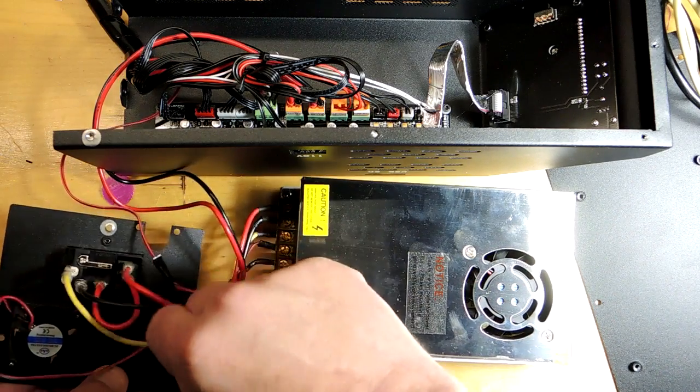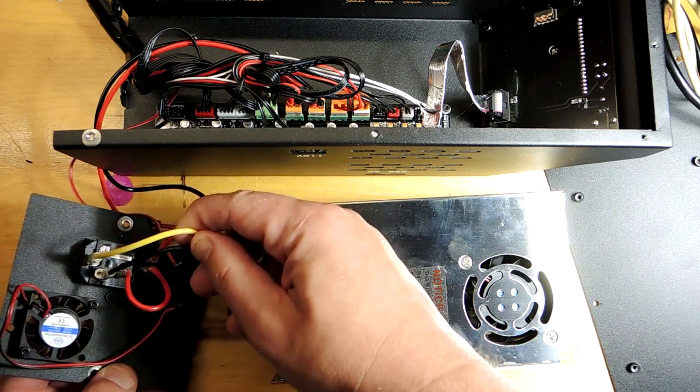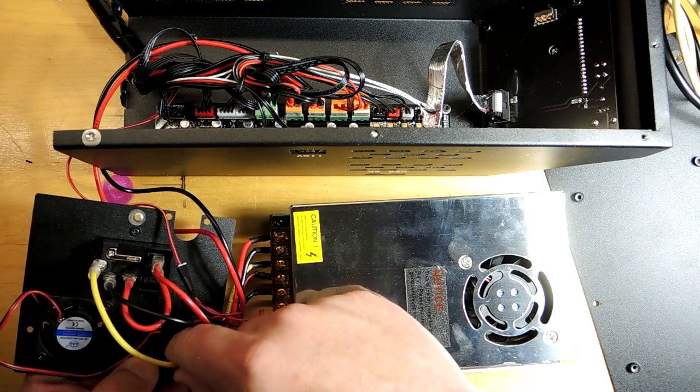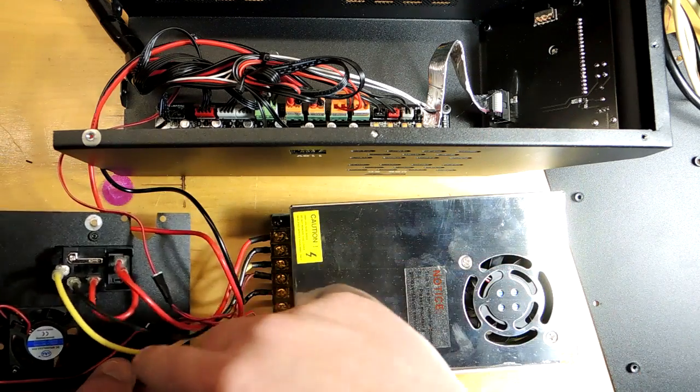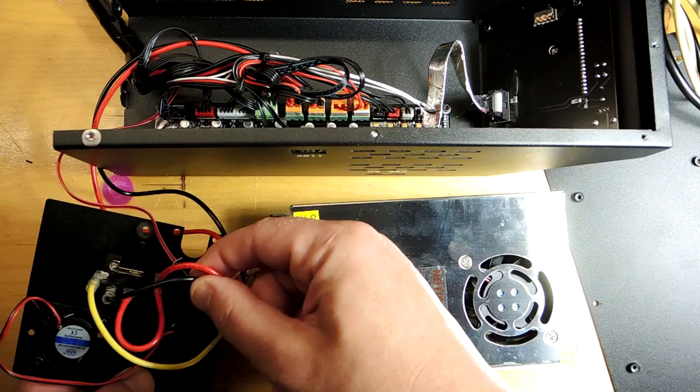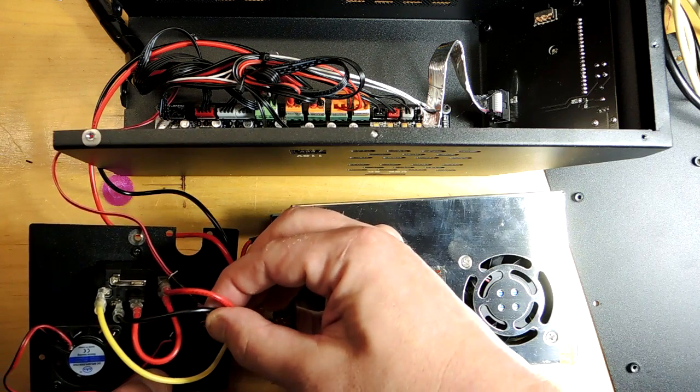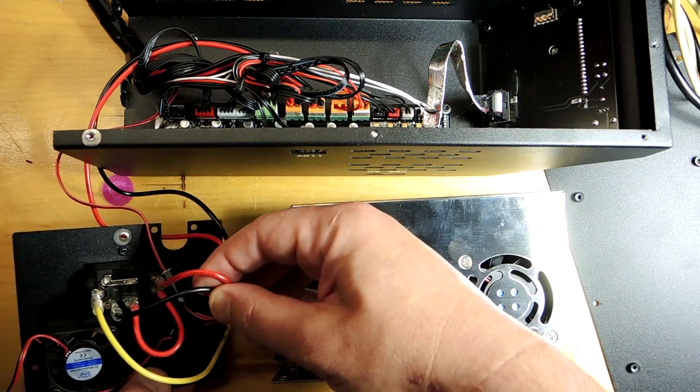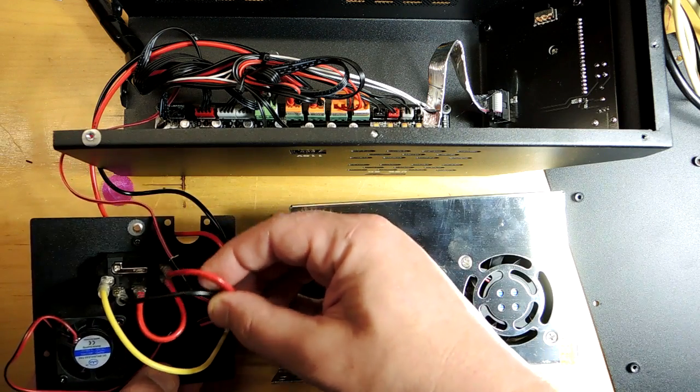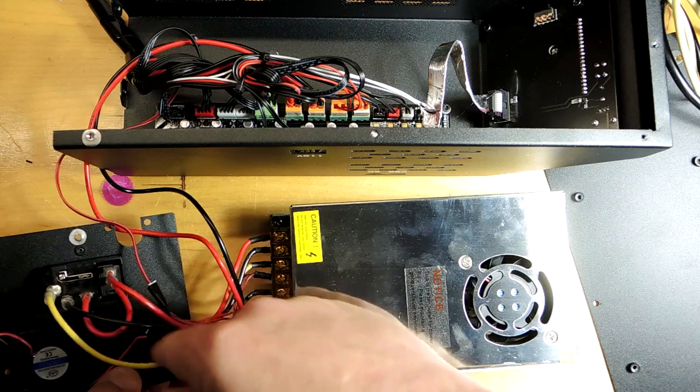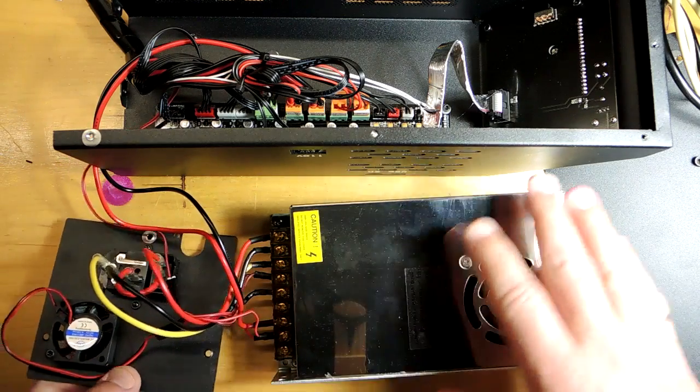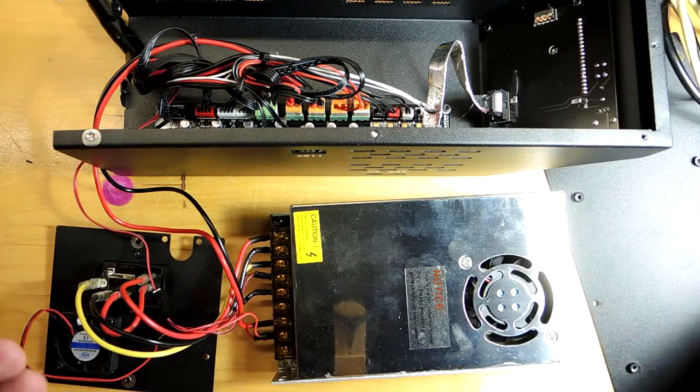The AC entry is here. The wire here is yellow. If it was European standard, it should be green with a yellow stripe. If it's North America, it should be green. So it's the wrong color, but so what? The same thing with the color here is black and red. If this was North America, it would be black and white. If it's Europe, it should be brown and blue. But no matter.